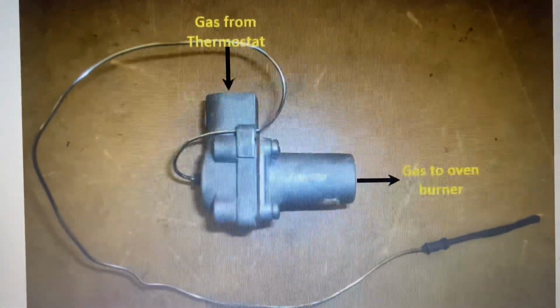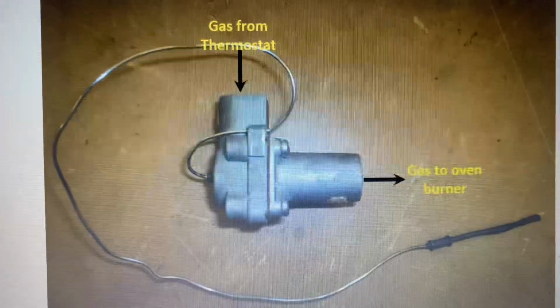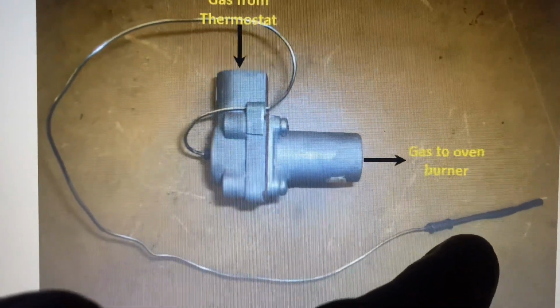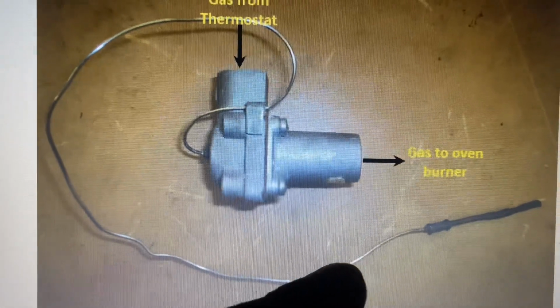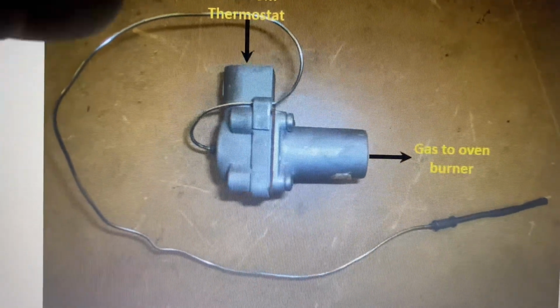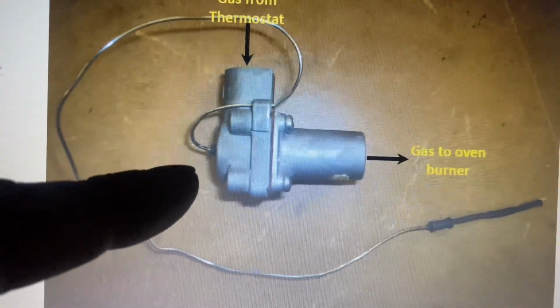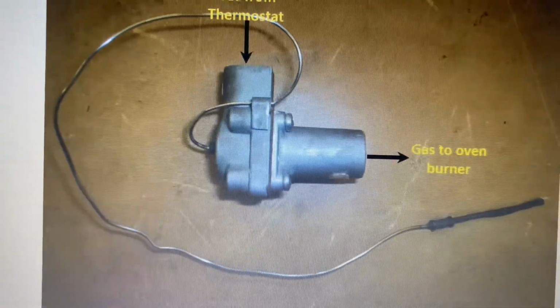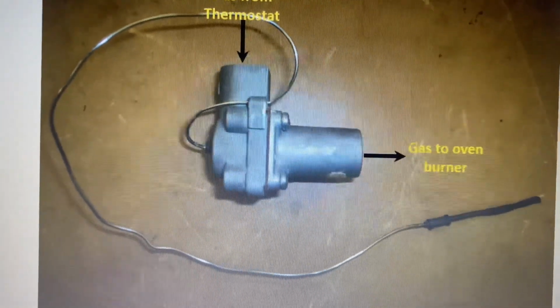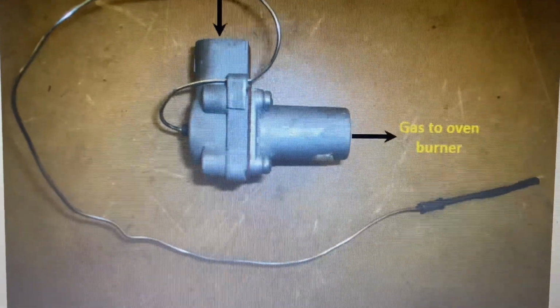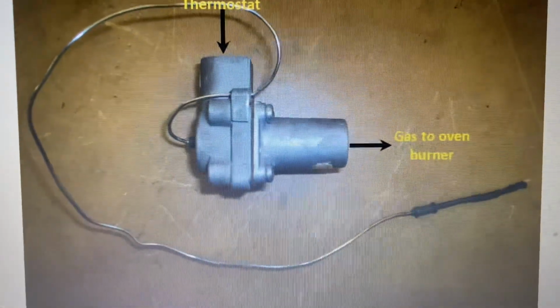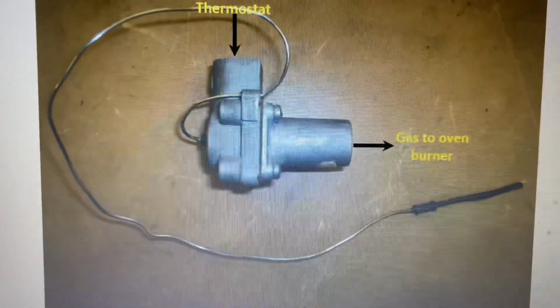So here's a photo of the flame safety device. That goes above the flame, above the burner, sends heat energy to the back of the valve, allowing the valve to open and close. So always make sure that's clean, there's nothing stopping the flame and the heat touching the probe.